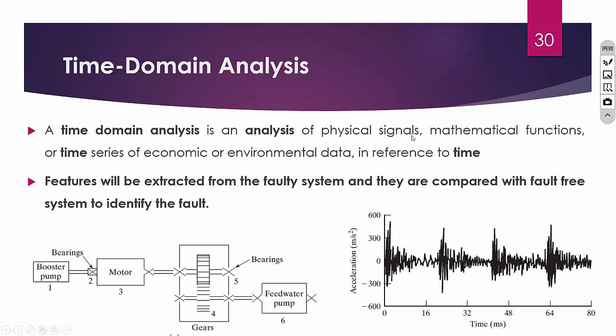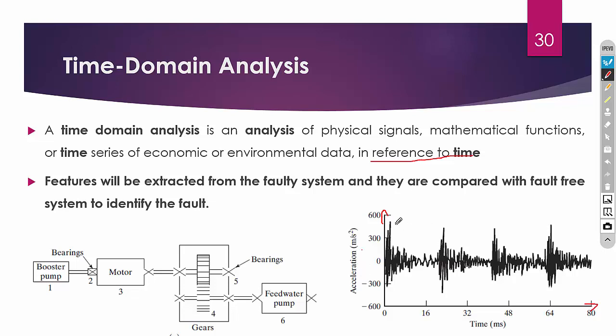Time domain analysis is the analysis of a physical signal, mathematical function, or time series with reference to time. We measure the signal with time as reference — the x-axis is time and the y-axis is amplitude, which may be displacement, velocity, or acceleration. The raw data taken from an accelerometer is in time domain format. From this data we can extract features such as the maximum value, minimum value, and mean value of the signal.